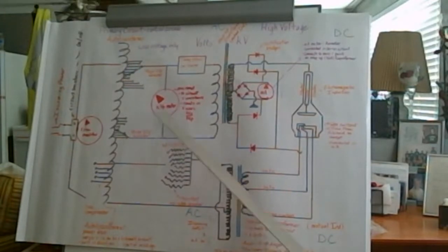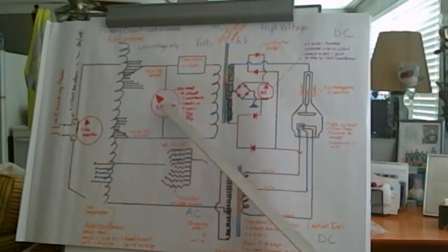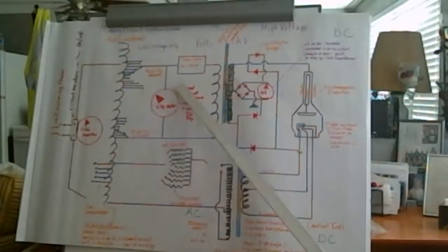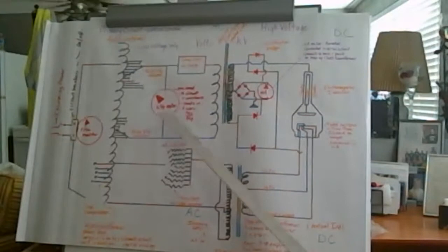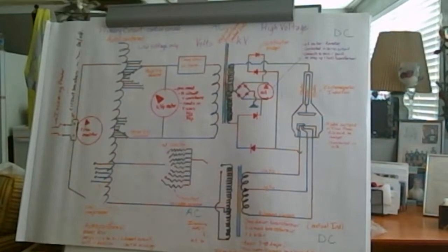Okay, and the kVp meter, in this circuit we're talking about, it is a parallel circuit. It's connected in parallel. That means the voltage is constant, and that means you can think of it kind of like a ladder, and if a rung is gone from the ladder, you could still feasibly use the ladder.